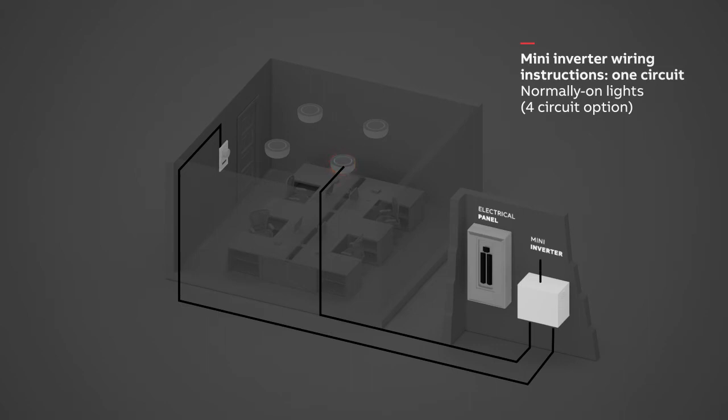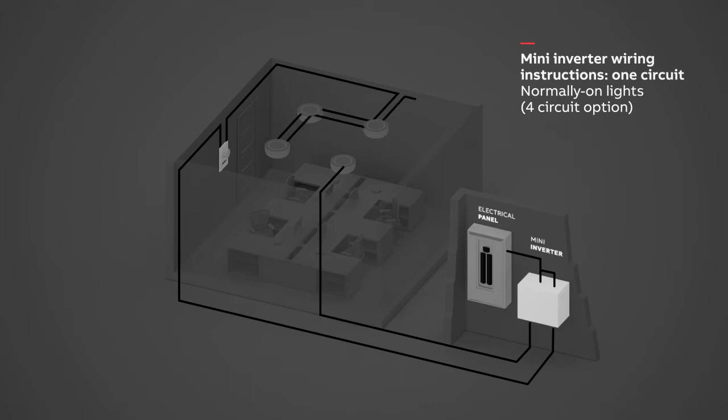Wire the switched and unswitched input of the Mini Inverter to the electrical panel. Wire the normal lights that will be controlled by the wall dimmer but will not operate as emergency lighting to the electrical panel.